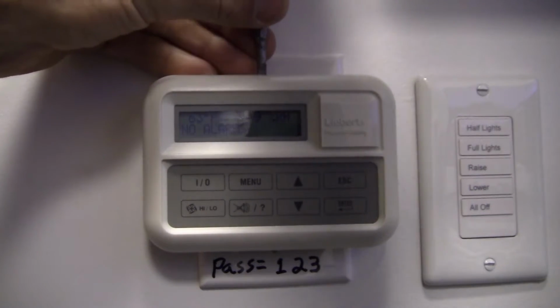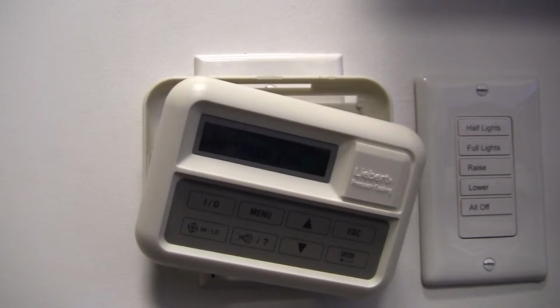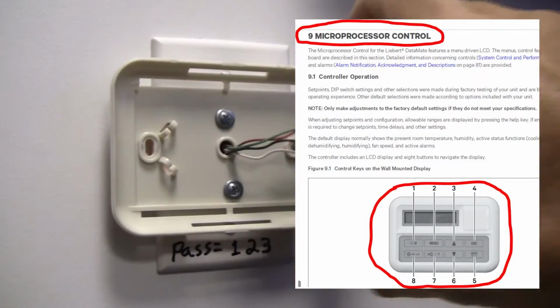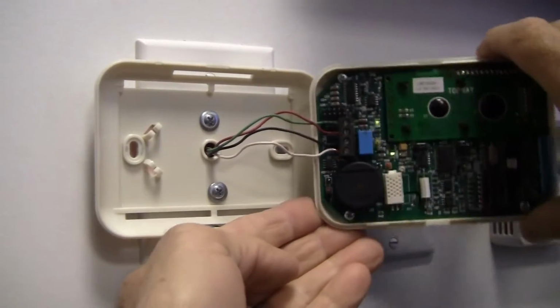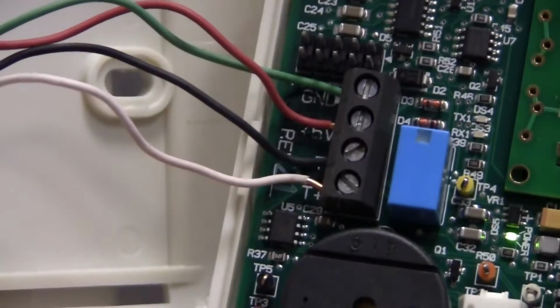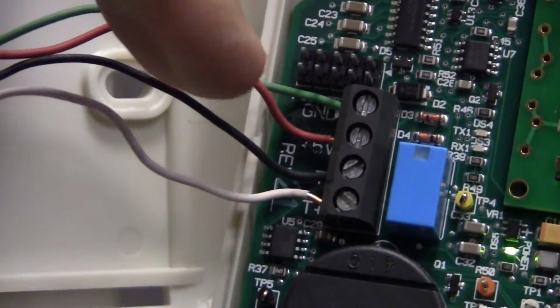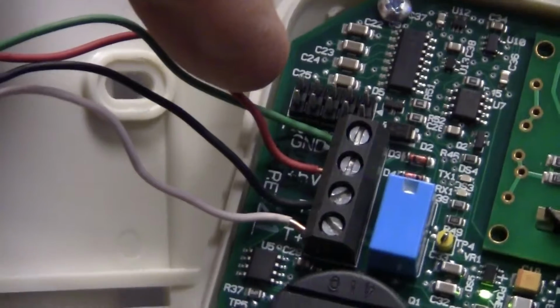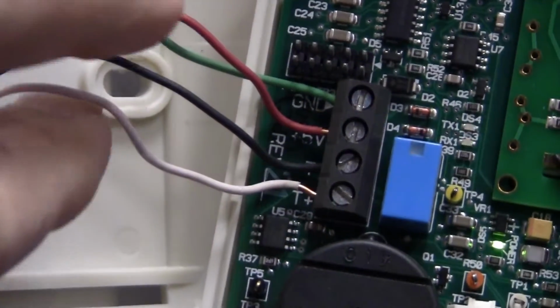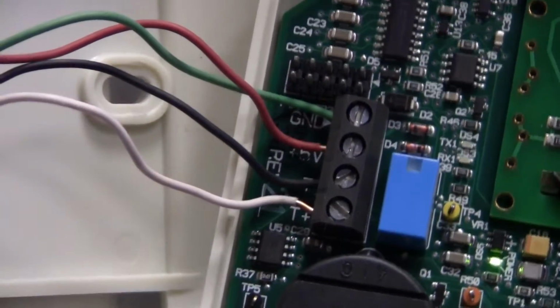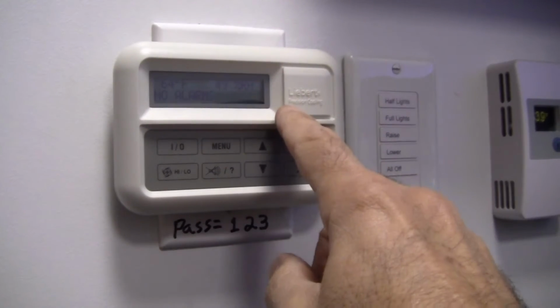Now this is not a standard thermostat. I think they call it a control panel interface. I'll put a note there with the exact wording. This is the wiring in the back. The green wire here is the ground. The red wire is a 5 volt, I think DC, signal. And the black and white wires are the communication wires going to the PC board over at the unit. So it's not like a standard 24 volt thermostat. I'll give you the model number in the video, but this control panel interface basically costs $1,400.